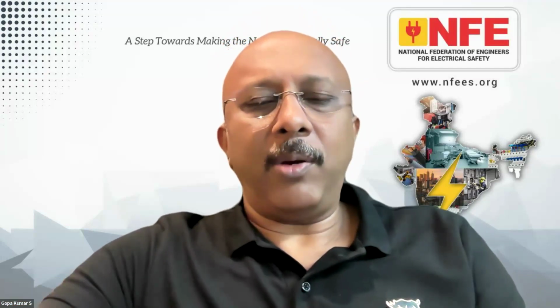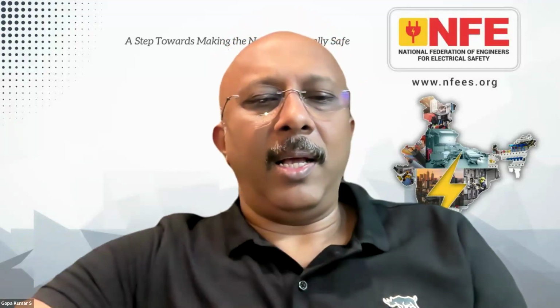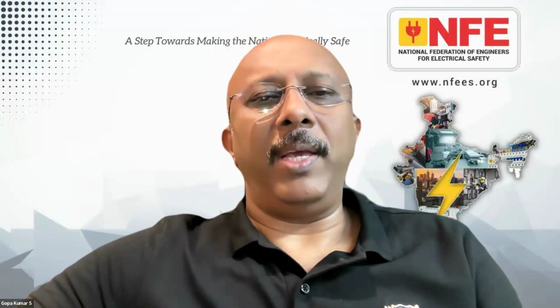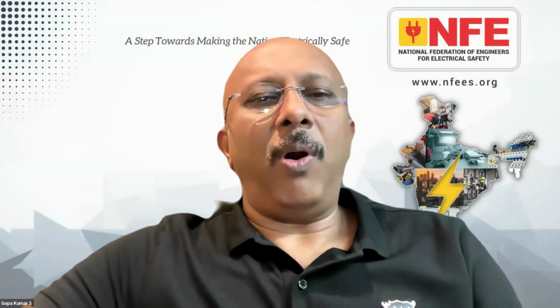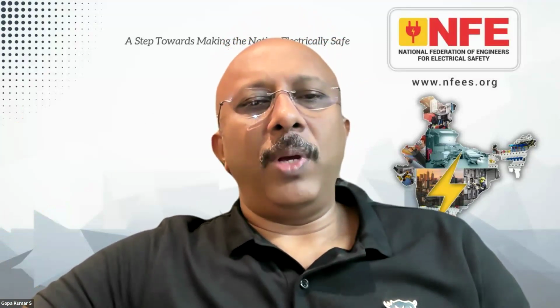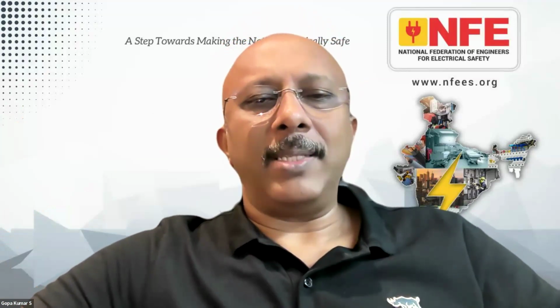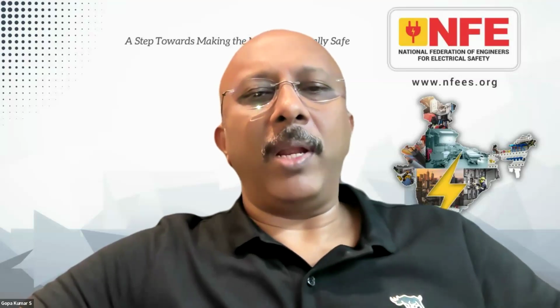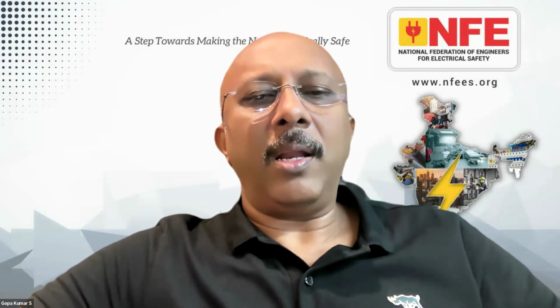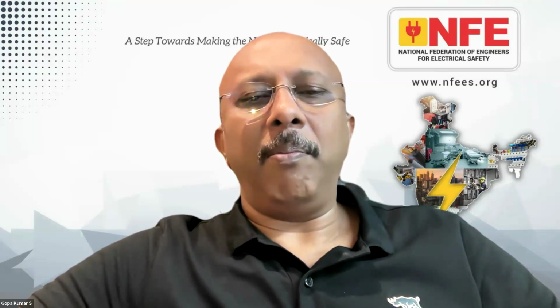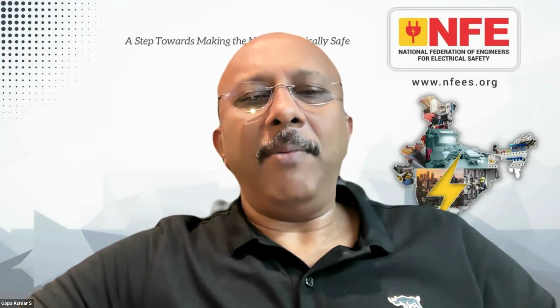Now, coming back to Krish, I have a question. Last week in Manila, in the IEC TC meeting, we had an interesting discussion on fault current calculation. In India, our practice is, for example, with the transformer and the main panel, we consider the DC resistance of the conductor and calculate the fault current. As a result, the fault current requirement is very high in the main panel, say 50 kiloampere or sometimes 65 kiloampere. As a result, protective devices of very high breaking capacities are used in those locations.